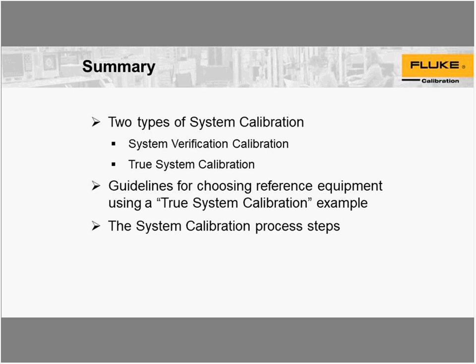Okay. Next is when you're using a dry well as the source and monitoring with an SPRT, where the SPRT is the reference, wouldn't the dry well also be listed as a standard on the certificate, since there are some uncertainties still contributed from the dry well? They would be part of the tolerance group, any heat source would be, but they're not listed, as you're doing a comparison calibration. It's the same as if you're using a bath.